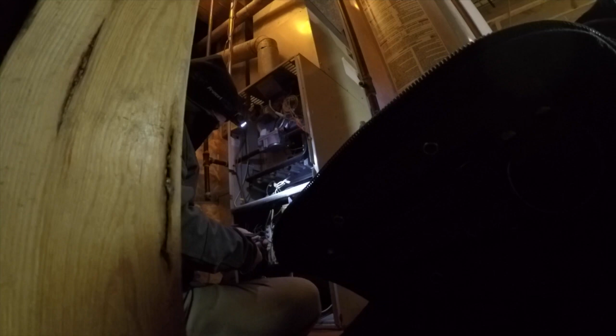Alright, so I've already watched one of the heating cycles go through, and what I discovered was the blower motor wasn't coming on when it was supposed to. So I'm checking to make sure it has low voltage, and trying to see if it'll come on if I give it a call for fan, and it's not. Then I double check - you see my meter sitting up on top there - I was looking for the high voltage, and it did get high voltage. So now I put my meter all the way to the back and checked the capacitor to make sure it's okay, and it was good. At this point I've decided I've got a bad blower motor.